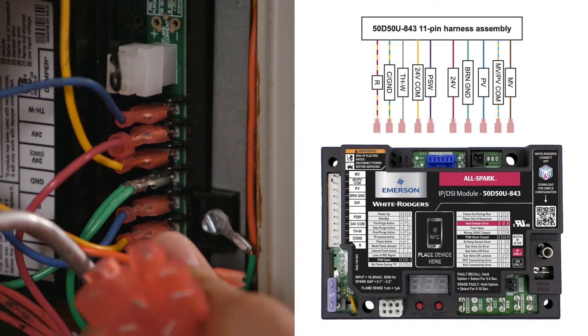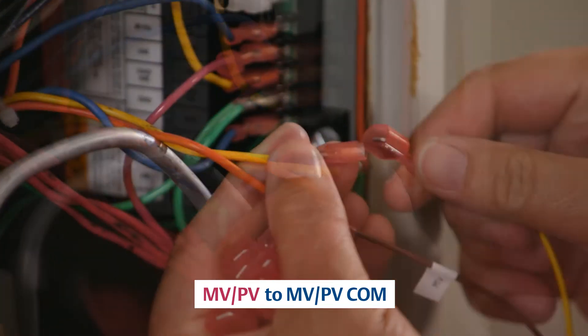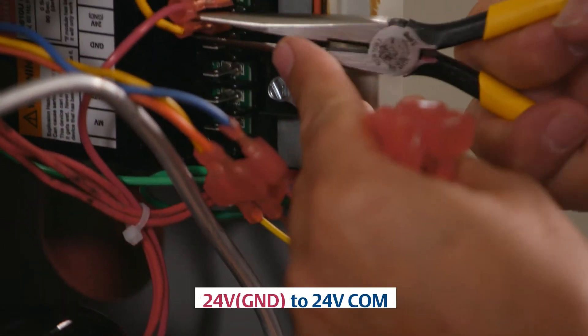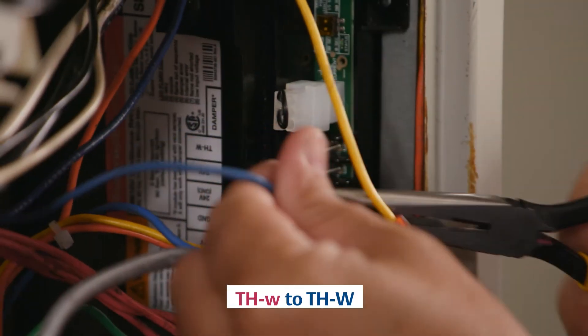Individually disconnect and transfer each wire from the existing control and connect it to the appropriate quick-connect terminal on the 50D50U-843 11-pin harness or dedicated spade terminal on the printed circuit board. Note in the instructions: when a module does not use both the 24-volt and THW terminals, install the 24-volt wire on the harness wire labeled THW. Connect MV to MV, MV-PV to MV-PV-COM, PV to PV, GND to BRN-GND, 24-volt GND to 24-volt COM, 24-volt to 24-volt COM, and finally THW.